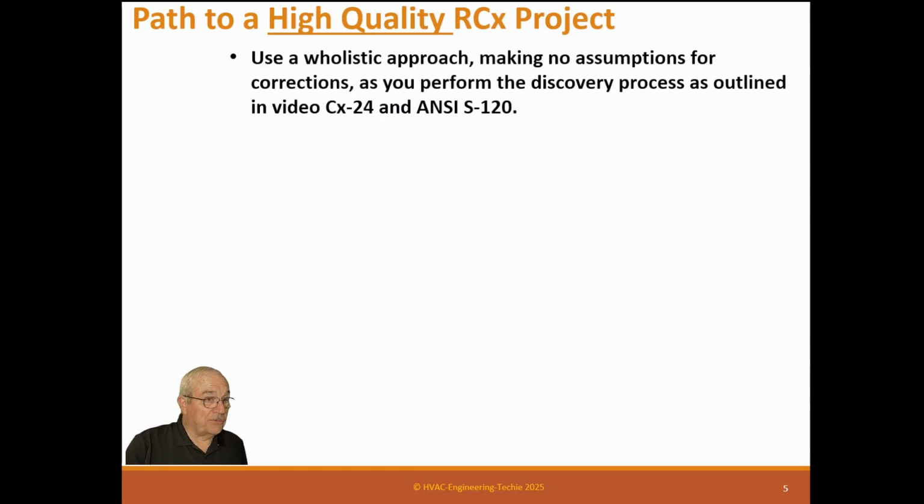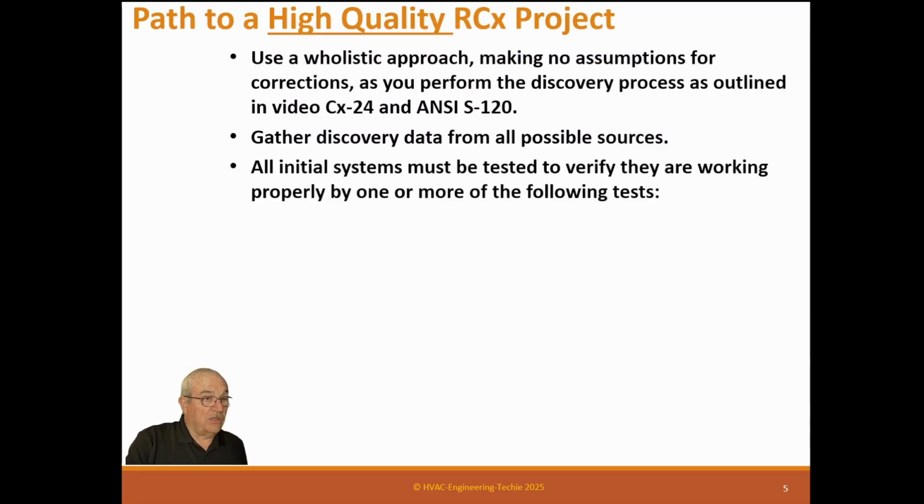It's the opposite of those things, obviously, but use a holistic approach, making no assumptions for corrections. As you perform the discovery process as outlined in video Cx-24, and of course in the ANSI standard, gather discovery data from all possible sources. Don't make judgments on just one piece of data you got. Make sure you look into everything around that issue to make sure you really know what its cause is.